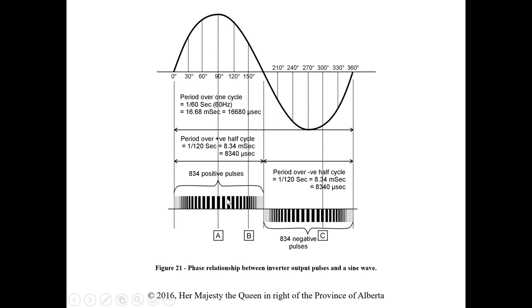At point A (90°) we want maximum voltage, at point B a value less than maximum but not zero on the positive side, and at point C an instantaneous value at 300°. The computer calculates instantaneous voltages at each point along the sine wave and adjusts pulse on/off times accordingly. It's not a true sinusoidal wave coming out, but it mimics it — the load essentially sees true AC output.